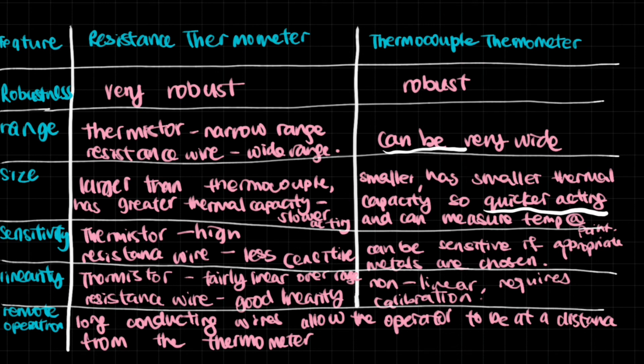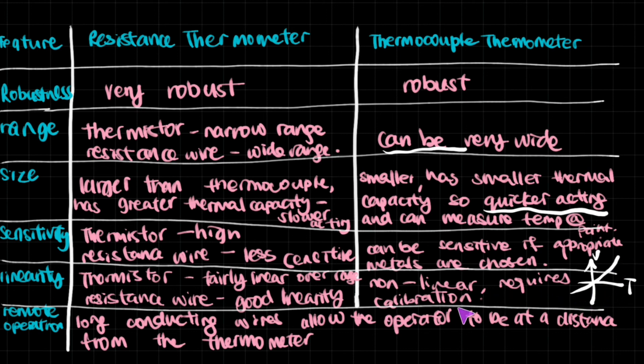For sensitivity: the thermistor tends to have very high sensitivity. Resistance wire is less sensitive but stable over a wide range. Thermocouples can be very sensitive depending on the metals used. For linearity: the thermistor is fairly linear over its range. Resistance wires have very good linearity, being stable over a wide range. Thermocouple thermometers are non-linear, as seen from the voltage-against-temperature graph which curves rather than being straight. This requires calibration — you need to add a linear scale to this non-linear voltage output.